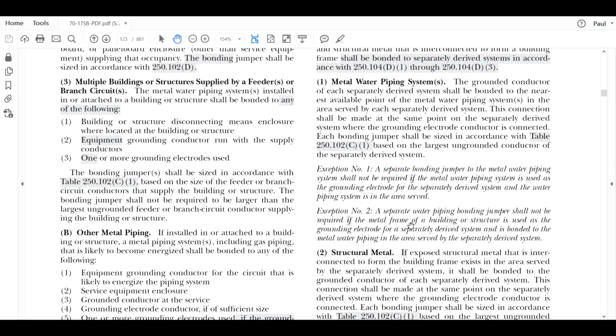And this one says, again, a separate water pipe bonding jumper shall not be required if the metal frame of a building or structure is used as the grounding electrode for the separately derived system and is bonded to the metal water pipe in the area served by the separately derived system. Basically, what that's telling me is I don't need to run a separate water pipe bonding jumper if that metal frame of a building or structure is actually being used as a grounding electrode for that separately derived system. And of course, that building and structural metal framing is actually bonded to the water pipe system in that area. And that's where you tie all of the electrodes together in a system. So obviously if both of these are there, the requirements in 250.50 require that you tie them all together.